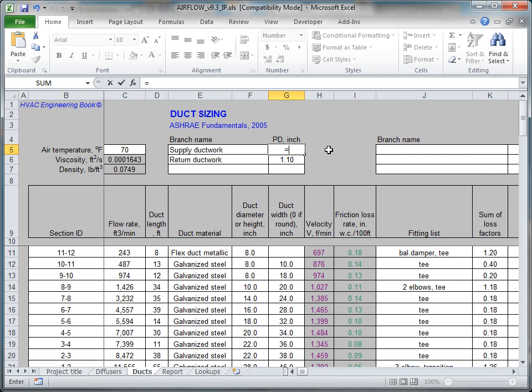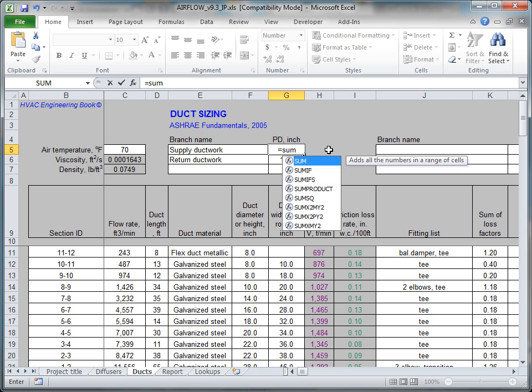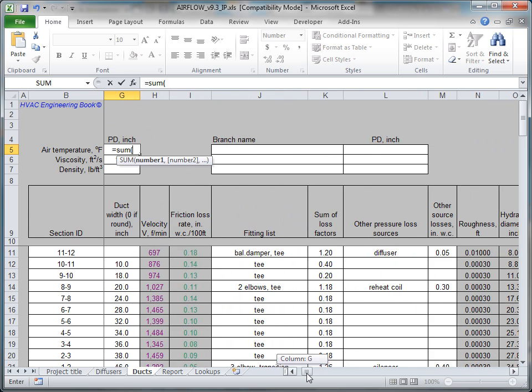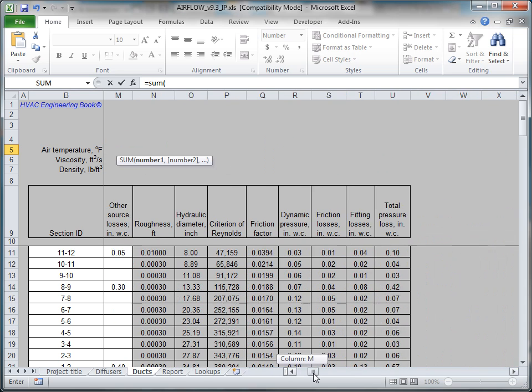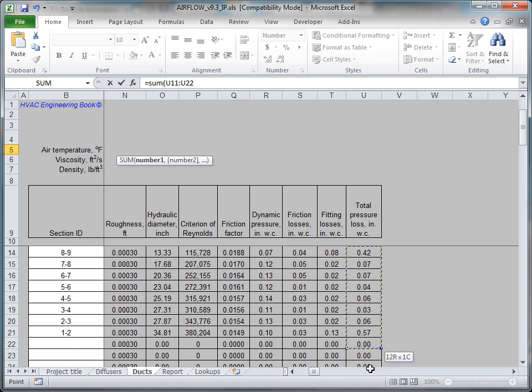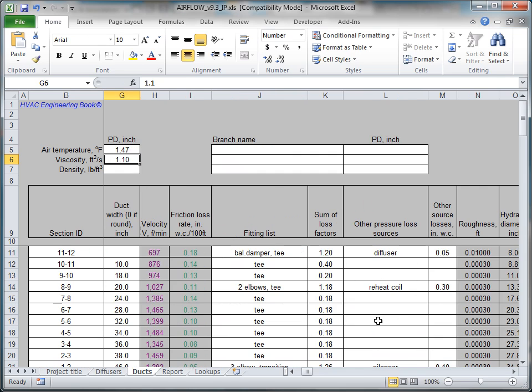To obtain the total static pressure requirement for this duct path, simply sum up all the section pressure losses from column U into cell G5. You will later use these pressure requirements to size the air handling unit.